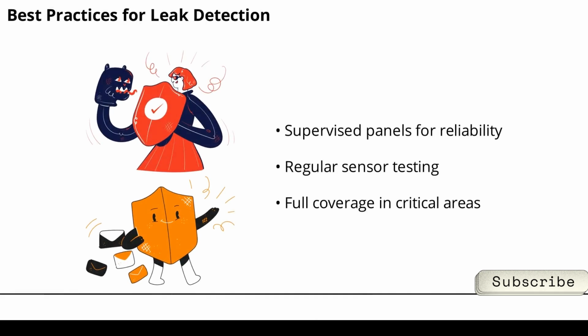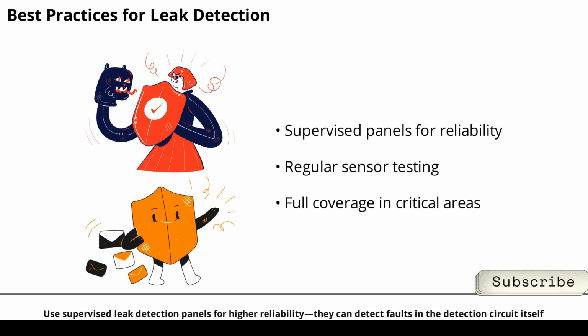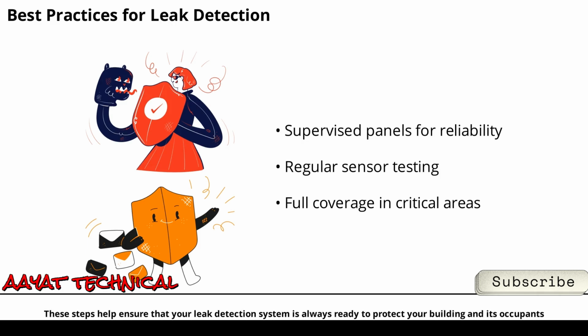To maximize the reliability of leak detection, follow these best practices. Use supervised leak detection panels for higher reliability. They can detect faults in the detection circuit itself. Regularly test leak sensors during scheduled maintenance to ensure they're working properly. Avoid placing control panels or IT equipment directly below water lines to reduce risk. In critical areas, use loop-type leak sensing cables for full coverage. These steps help ensure that your leak detection system is always ready to protect your building and its occupants.